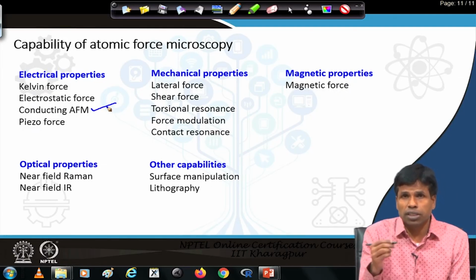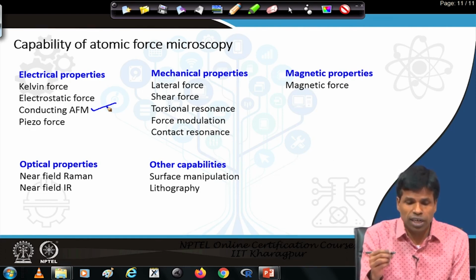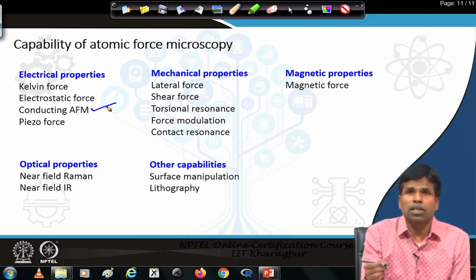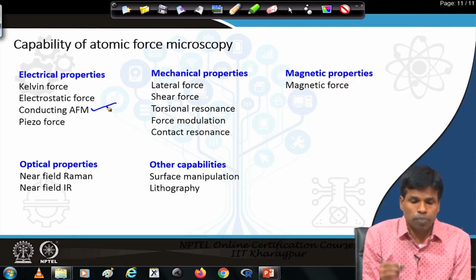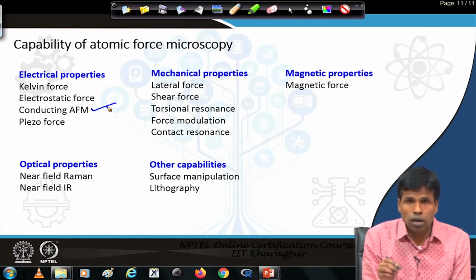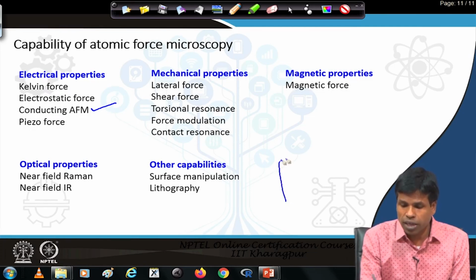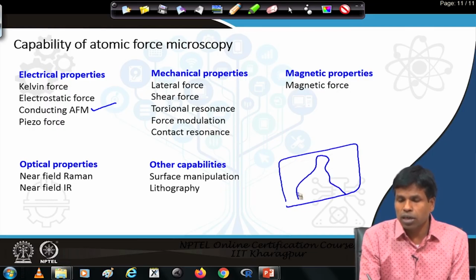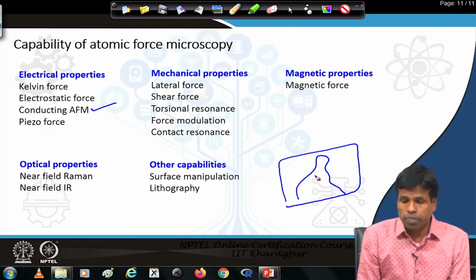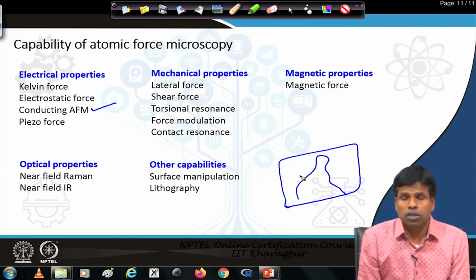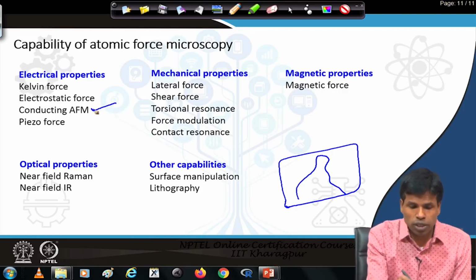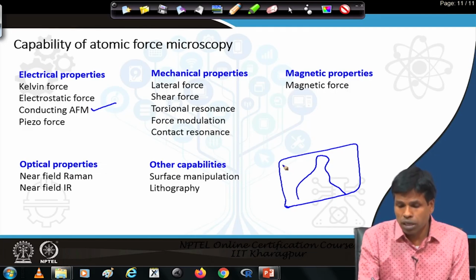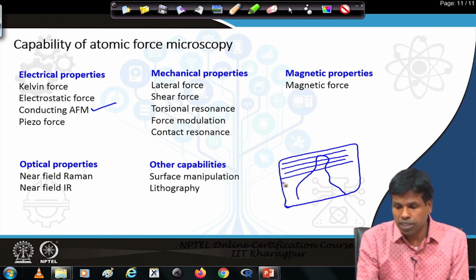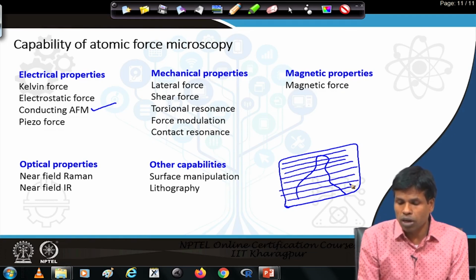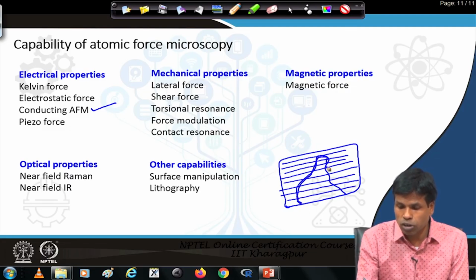In case of conducting AFM, the tip has to be conducting in nature, though theoretically we do not need a conducting tip, as we have seen in the first invention they used a diamond tip. But if we want to study the electrical properties of a sample, let us say on an insulating substrate we have conducting wires placed in a particular manner, or this kind of conducting layer is present in the sample with a particular distribution or arrangement, then we can use a conducting tip and measure the current passing at different regions across the sample and get information on where this conducting layer is present on the sample.